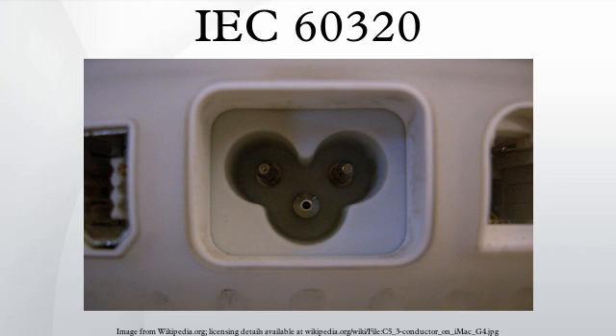Interconnection couplers allow a power supply from a piece of equipment or an appliance to be made available to other equipment or appliances. Couplers described under these standards have standardized current and temperature ratings. Different types of connector are specified for different combinations of current, temperature and earthing requirements. Unlike IEC 60309 connectors, they are not coded for voltage. Users must ensure that the voltage rating of the equipment is compatible with the mains supply.